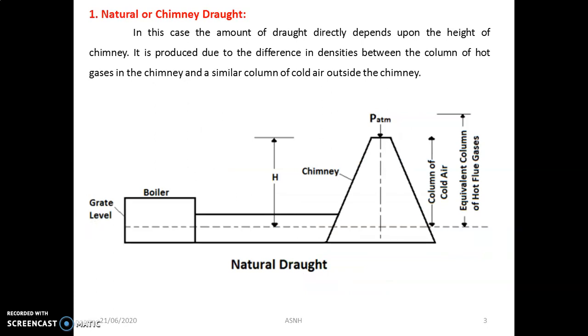The first type is natural draft, also called chimney draft. In this case, the amount of draft is directly dependent on the height of the chimney. It is produced due to the difference in density between the column of hot gases in the chimney and a similar column of cold air outside the chimney. In the boiler furnace, the grate is the area where combustion of fuel takes place, and the flue gases produced continuously move through the chimney and are exhausted to the atmosphere. No pump, blower, or fan is used — because of the density difference, air moves naturally. That is why it is called natural or chimney draft.